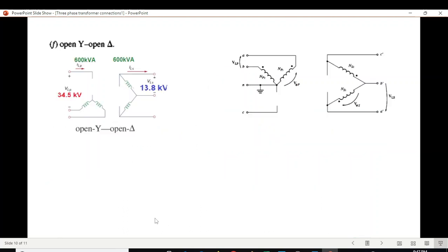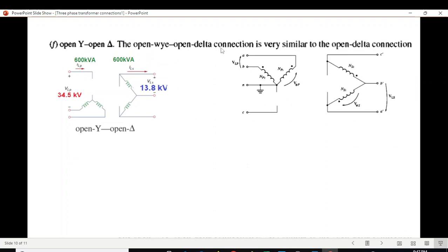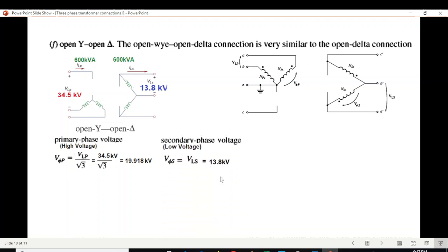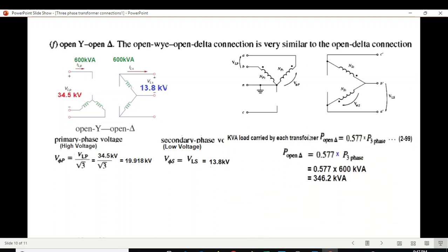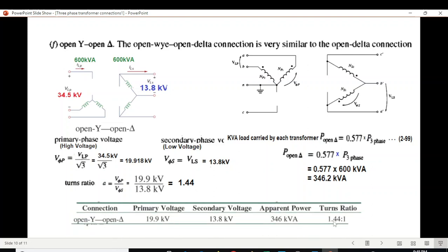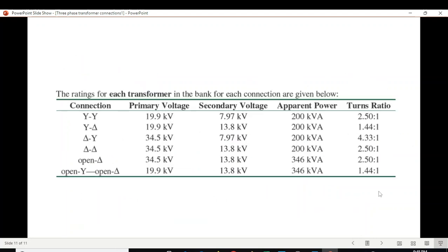For open-Y open-delta, we open one terminal on the Y side and one on the delta side. The open-Y open-delta connection is very similar to open delta. The Y-side phase voltage is line voltage divided by √3, giving 19.9 kV, and the delta-side phase voltage equals the line voltage of 13.8 kV. The apparent power per transformer is also 346.2 kVA, and the turn ratio is 1.44.